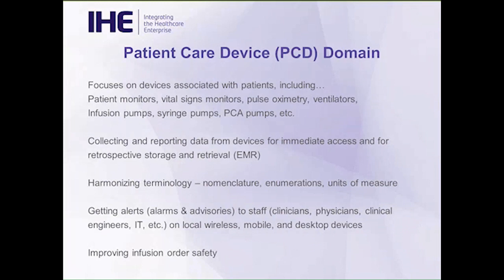The focus of PCD is on devices associated with patients, including patient monitors, vital signs monitors, pulse oximeters, ventilators, infusion pumps, syringe pumps, PCA pumps, etc. That's our focus, but we've broadened that out a bit in getting information from things like medical device management systems and location services.